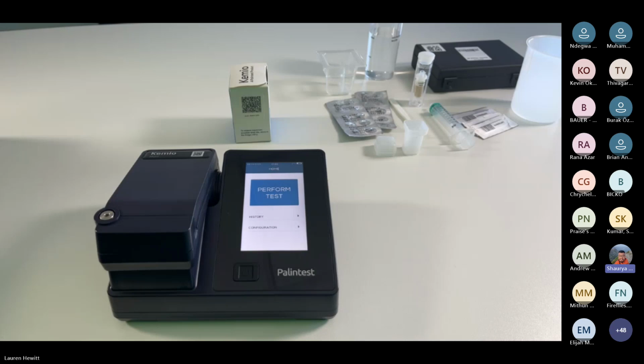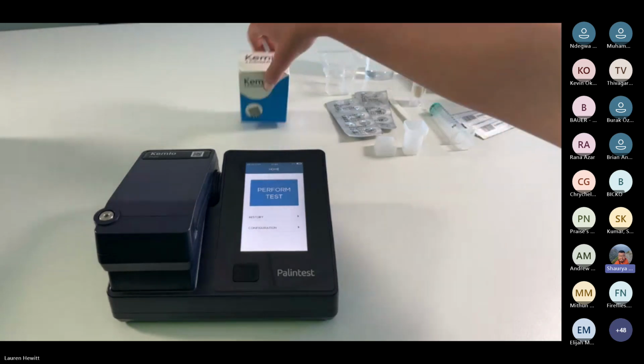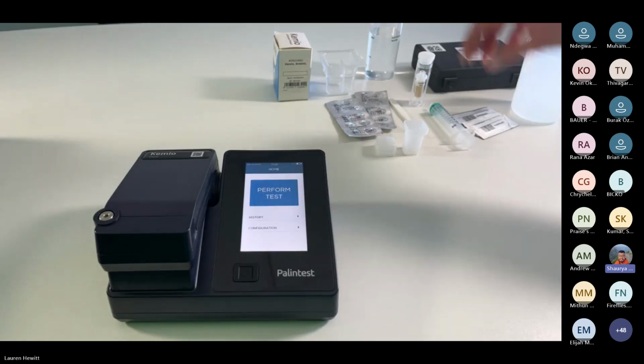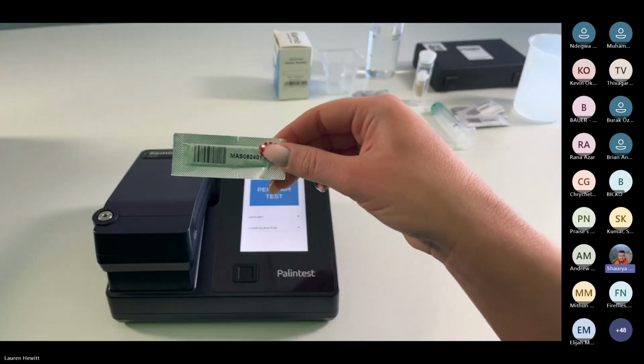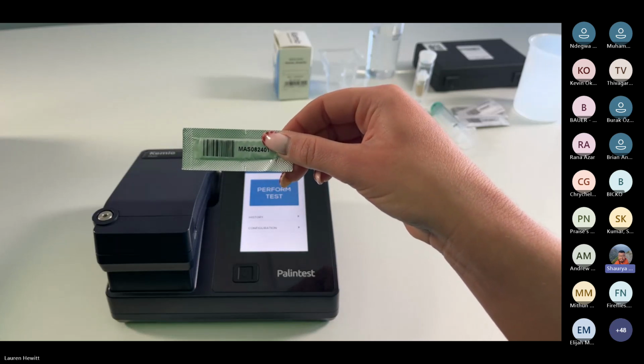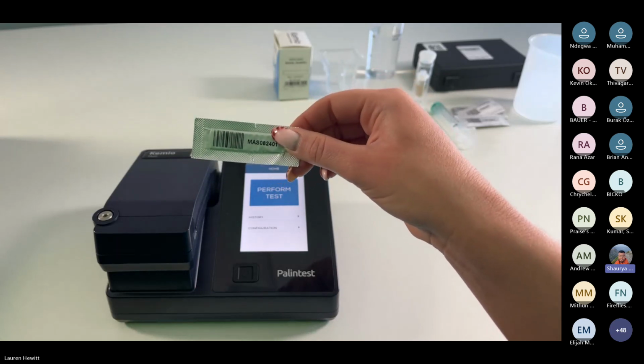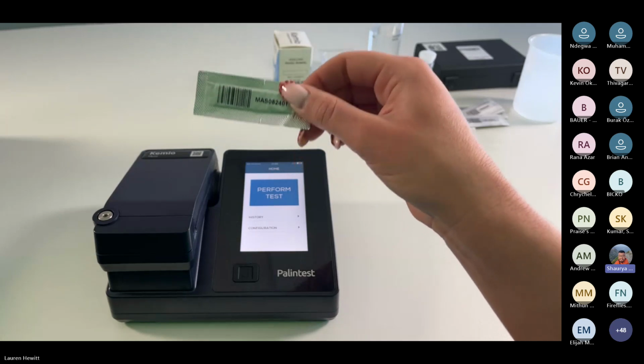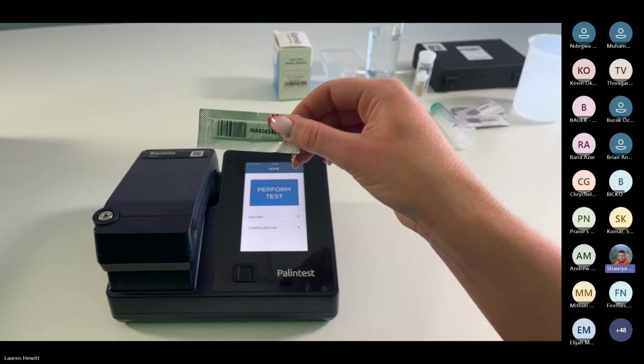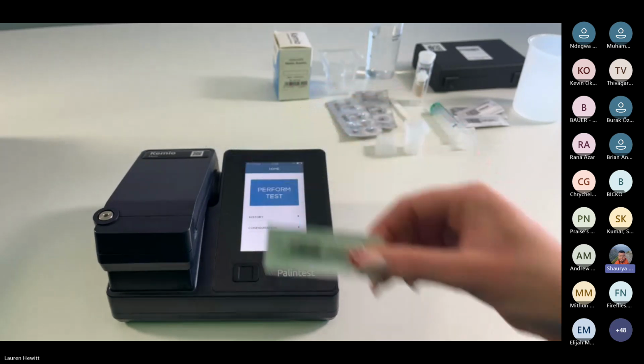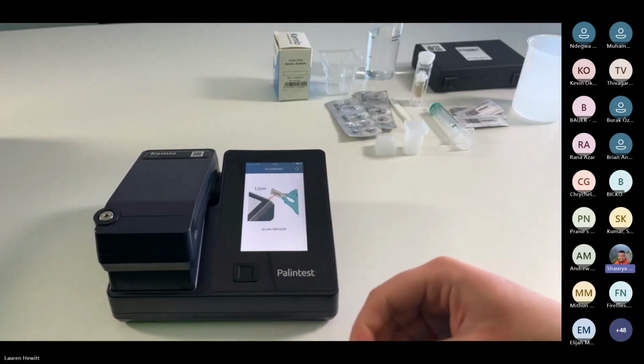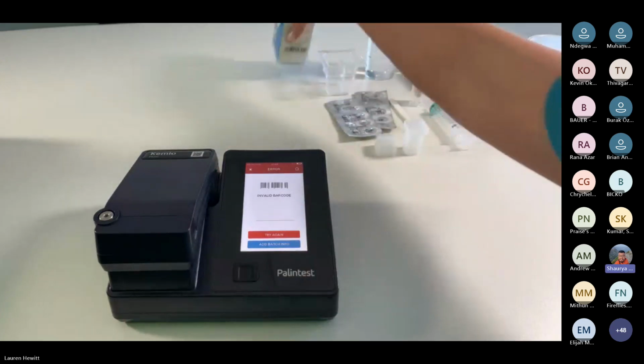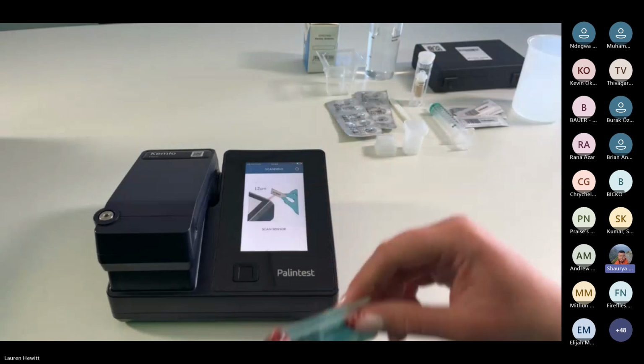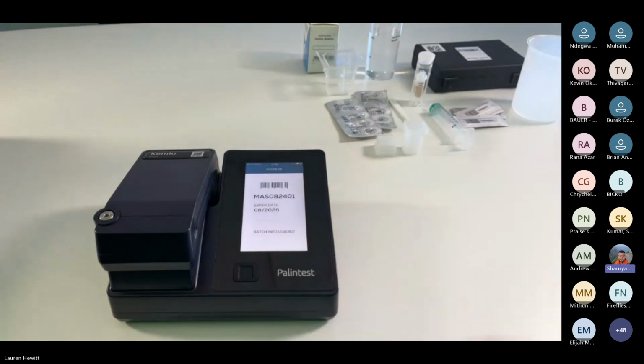And this is the same for any test being performed on the device, but today we're going to concentrate on arsenic. So now you've scanned in the QR code, you want to scan in the sensor. So the sensors inside of the box look like this, and they have a scanning code on the outside, a barcode. Now this barcode is really important because this is what links the test to the QR code. So this is what links the calibration, ensuring you get accurate results. So if we press perform test again, it would come on. Sorry, that was that in the background. If we try again, that now scans the sensor.